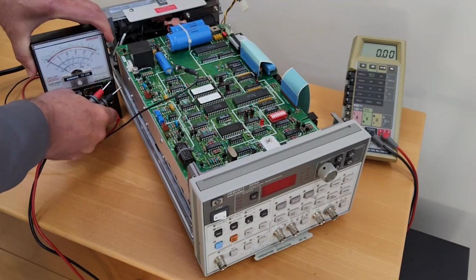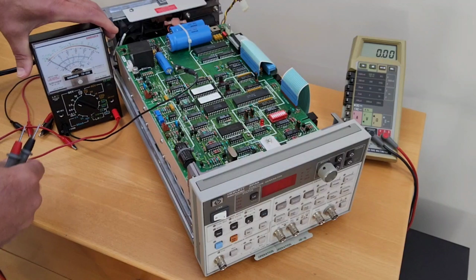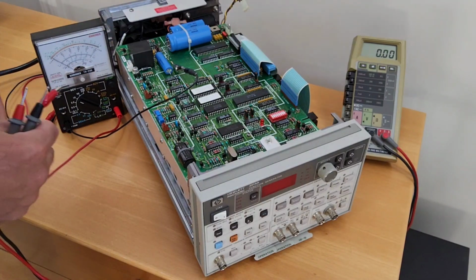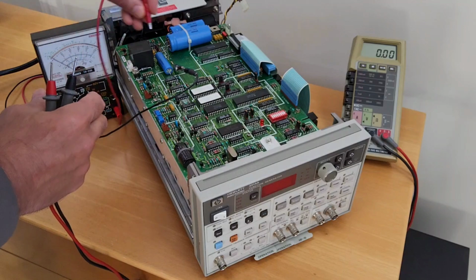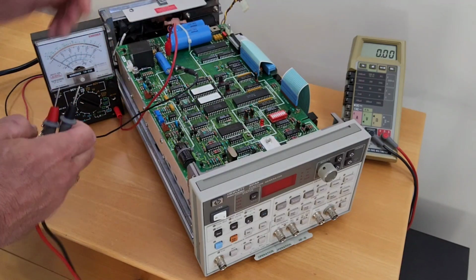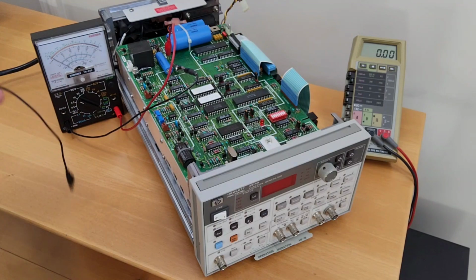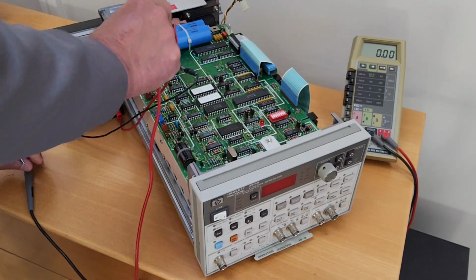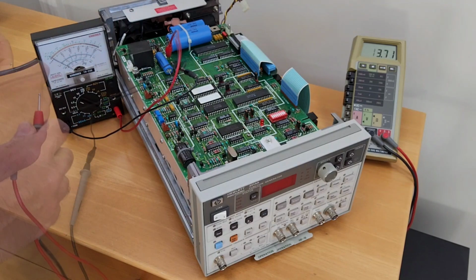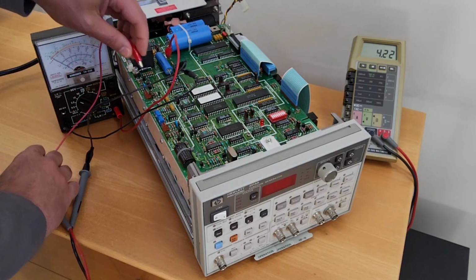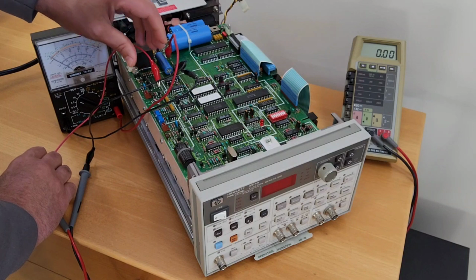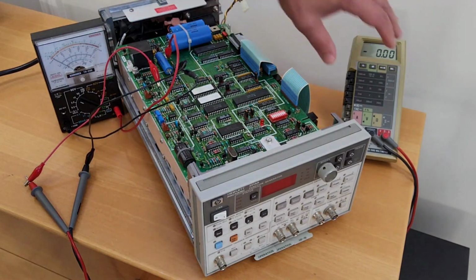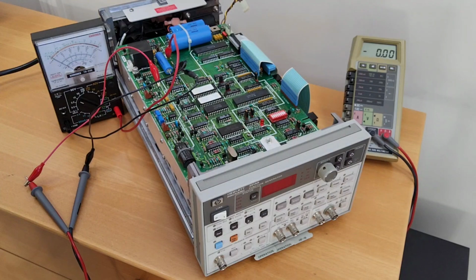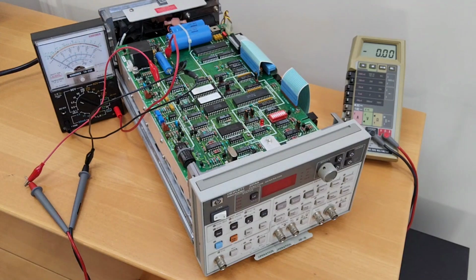So next I'm going to set my analog meter to 10 volt scale. So 5 volts should be right in the center. And there's already a 5 volts checkpoint tab here, so we could use that. And for minus 15, I'll use the digital meter. We'll use the same ground, and we use the minus 15 checkpoint on the board. And we take the meter out of AC, put it on DC, and we will connect this back on. And with a little bit of luck, hopefully we'll have a safe power on.